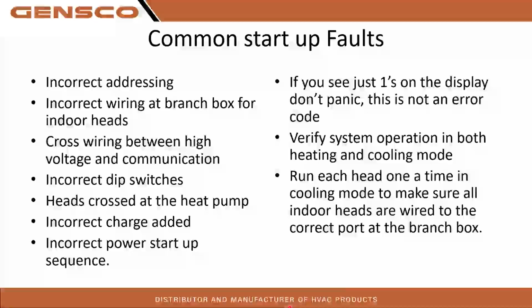Incorrect charge added. Like I said, with these units, you have to add charge no matter what, so be aware of that. I would highly, highly recommend and encourage you to write the total charge or the additional charge on the outdoor unit, like inside the cover. That way, when a service tech is coming back or anybody's following up behind you, and they're questioning, or I'm questioning them, "Hey, did anybody ever add any charge to the system?", they can find out right away. It's really annoying when we're having performance issues and we don't know if the installing team ever actually added the charge or not. Writing down what you added is going to help out your service guy a lot, and us.